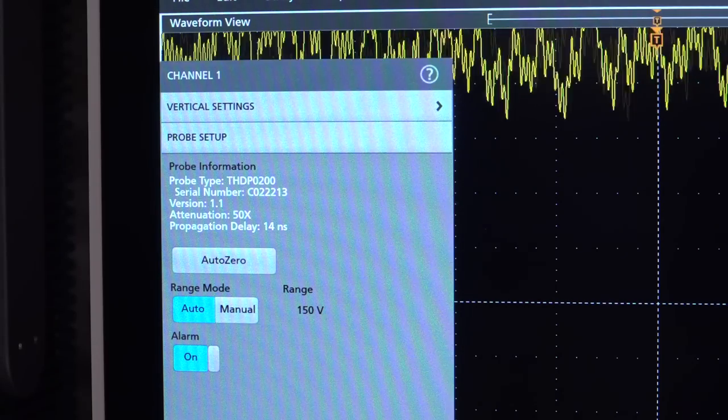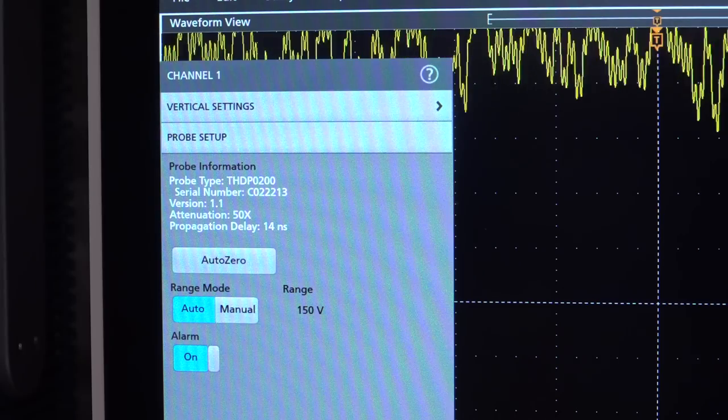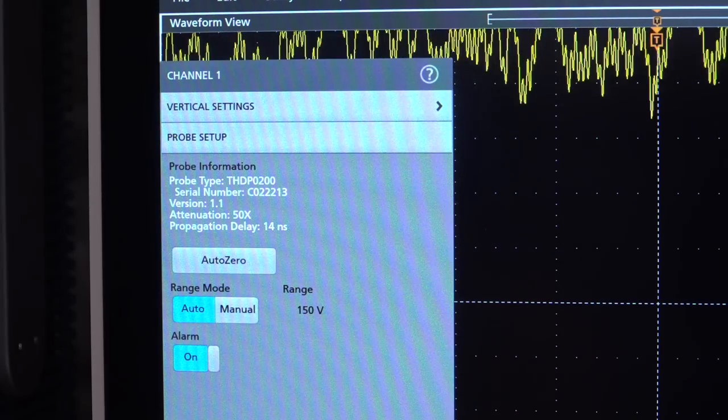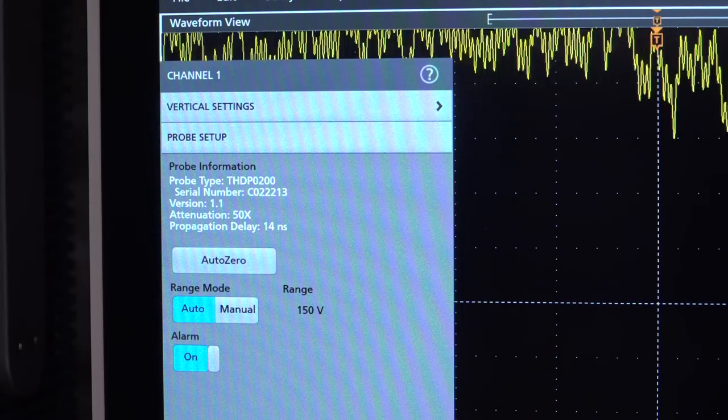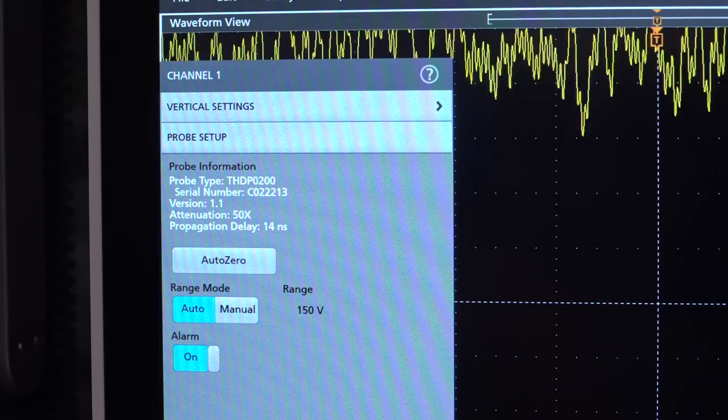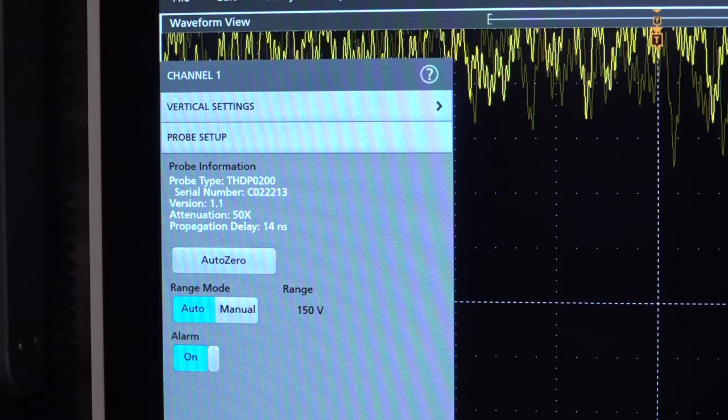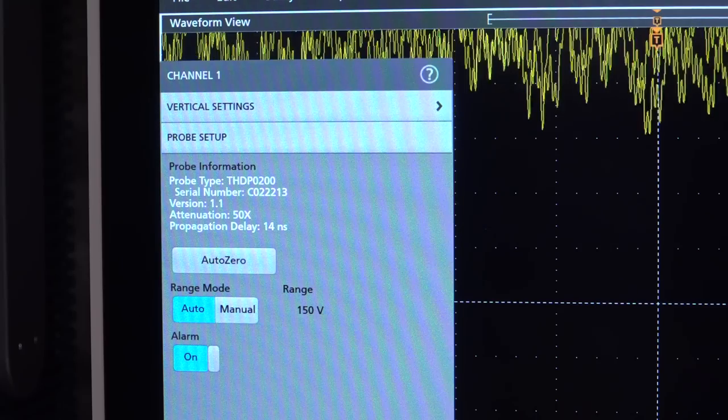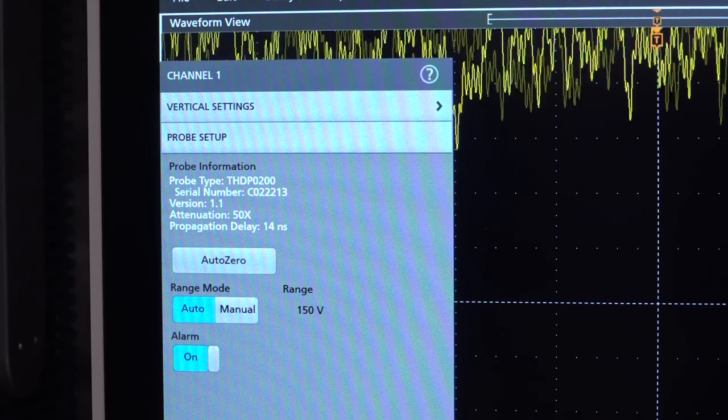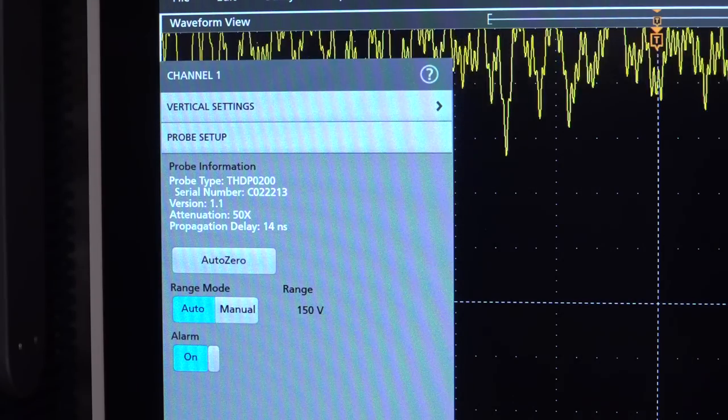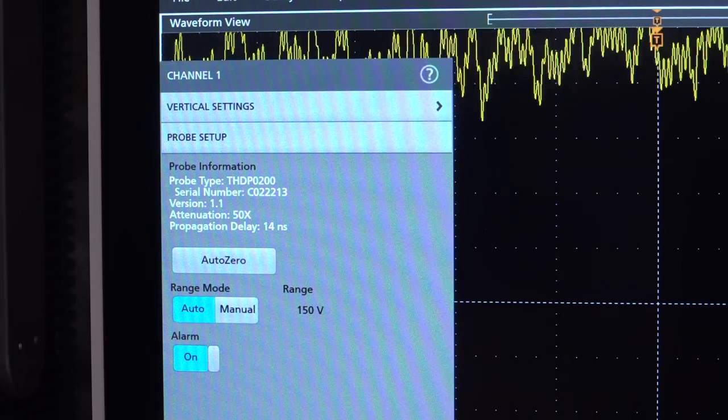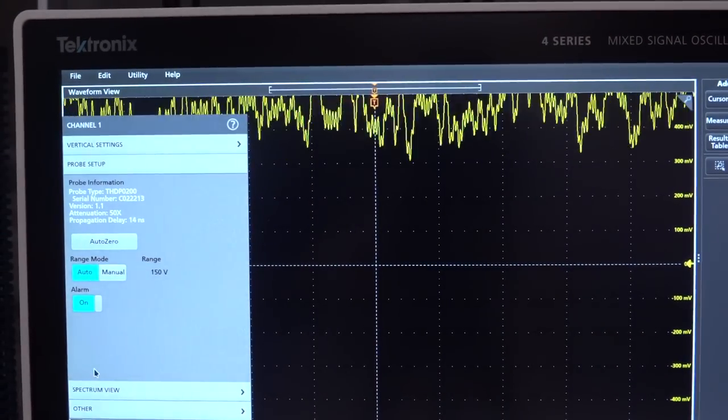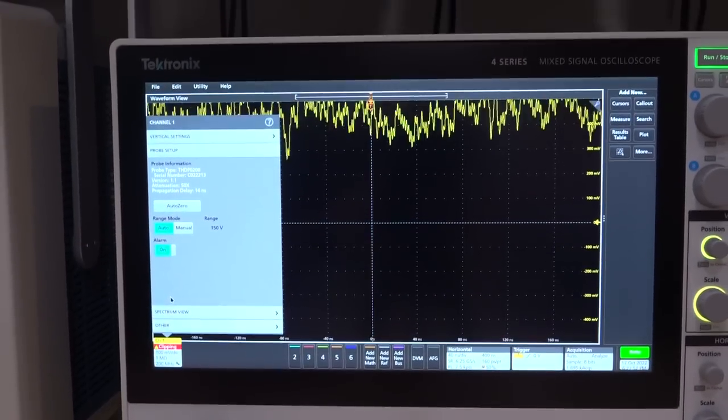That means that EEPROM must be completely corrupted and it must have another way of knowing what probe model it has. Maybe it uses a combination of resistors on the actual printed circuit board. If you think about it, that kind of makes sense because this way they will only have to download one firmware in all the probe models, both in the body and the PCB, and they just perhaps populate a different resistor in a different location to tell the microprocessor on the probe body which one is being selected. This is very interesting. I guess there's only one thing to do. We have to try and test it to see if it's actually working or not.